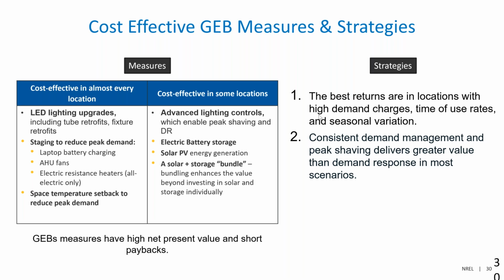In some locations it was also cost-effective to look at advanced lighting controls, where you could dim lights to an unperceivable level but find savings to enable peak shaving and response to specific demand response (DR) events. Electric battery storage is cost effective in some locations, as is solar PV, and a bundle of the two can enhance the value further.